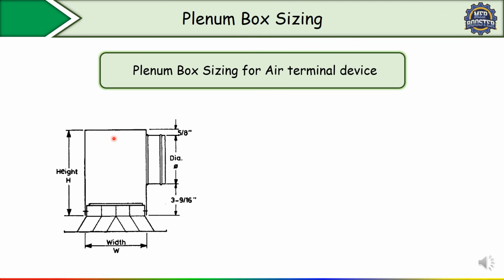Now the question is, if the plenum box is connected to an AHU or FCU, we can do the sizing using the discharge flow rate formula and the velocity I have told you. But if you are using a plenum box over a diffuser, how do you find out the height, the opening diameter and the width? Once you have done the sizing and selection of the diffuser, it is based on the diffuser neck size. You know that this diffuser has two sides: first is the neck and this one is the face. The face side is generally exposed to the room, and the plenum has to be connected to the neck.